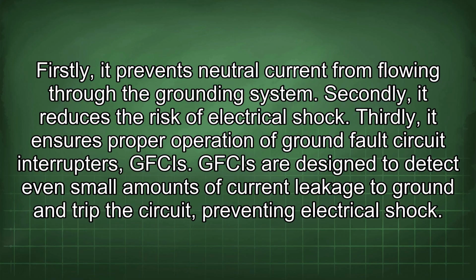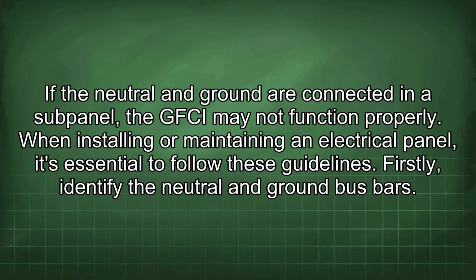Thirdly, it ensures proper operation of ground fault circuit interrupters, GFCIs. GFCIs are designed to detect even small amounts of current leakage to ground and trip the circuit, preventing an electrical shock. If the neutral and ground are connected in a subpanel, the GFCI may not function properly. When installing or maintaining an electrical panel, it's essential to follow these guidelines.